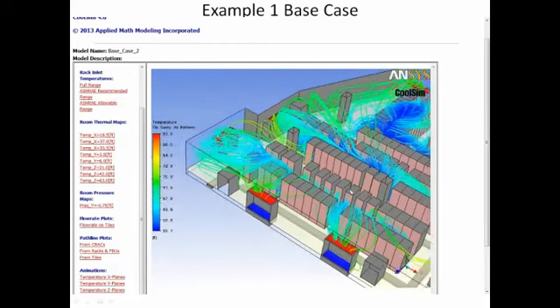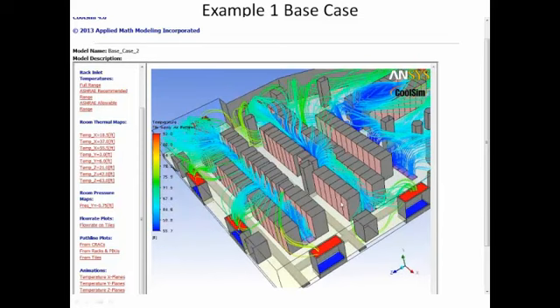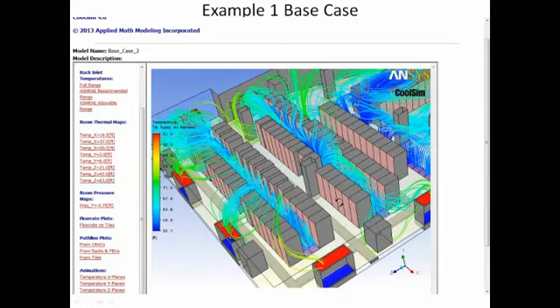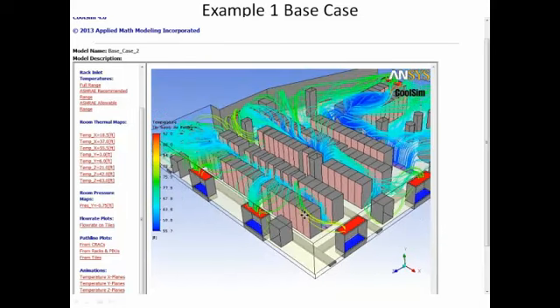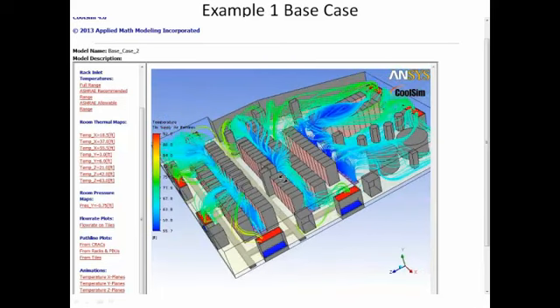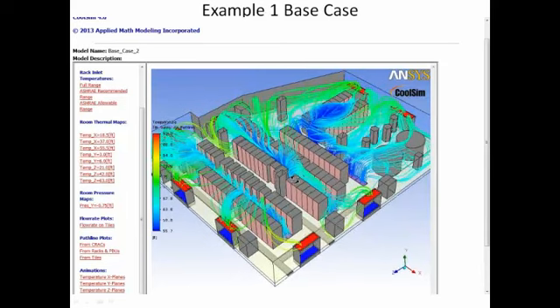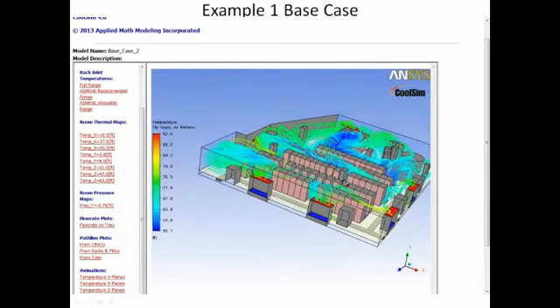I think this, Paul, points out the important fact that any data center has to start out with a solid design, because if you don't have a solid design from the beginning, it's going to be very difficult to fix it. But say that you have a solid design. For example, in this case, you have real problems: when one CRAC is delivering the intake air to another CRAC, that's not going to be efficient. And you also haven't installed blanking panels, so there are gaps between the racks. And that's where you just showed that you get recirculation. So those are two challenges, at least in this data center.